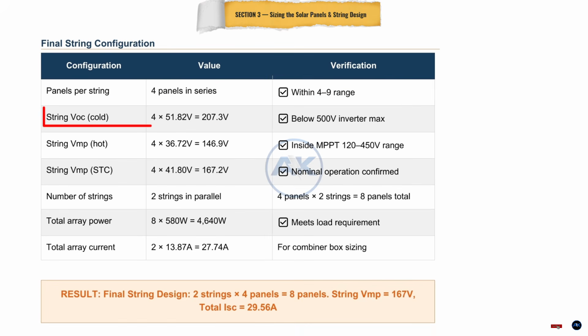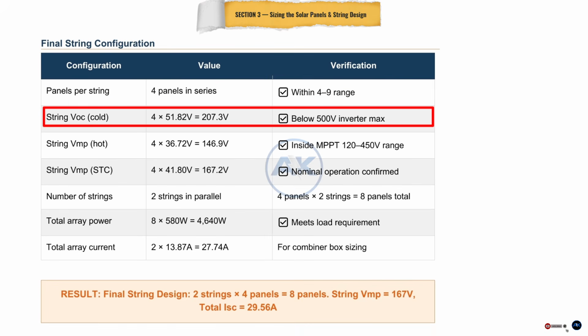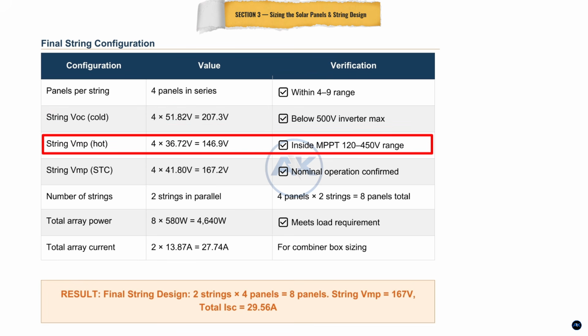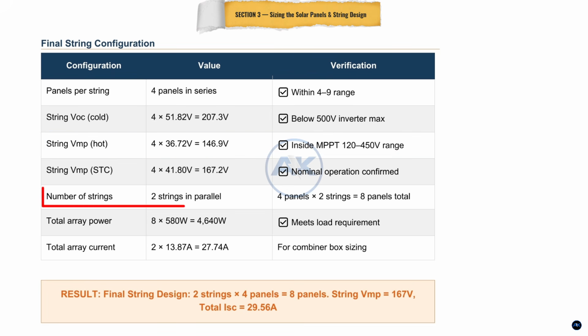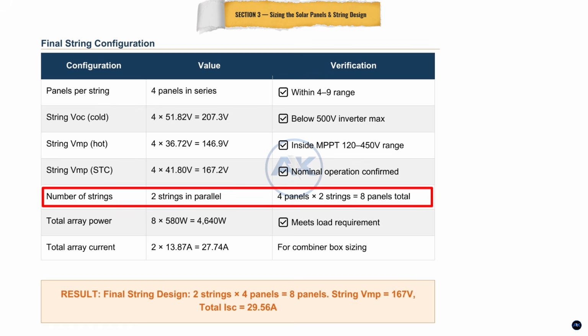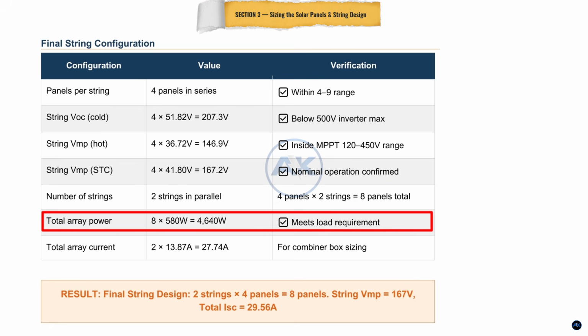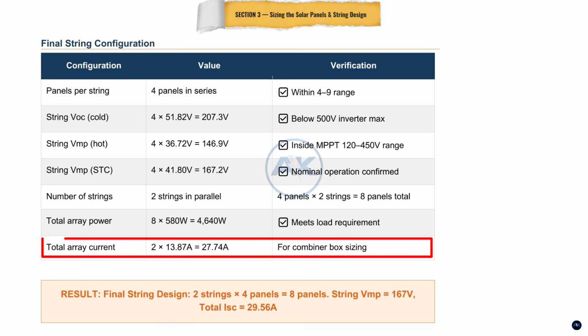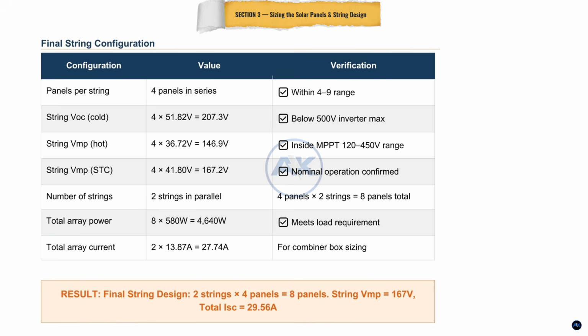String VOC cold is 207 volts, safely under 500. String VMP hot is 147 volts, inside the MPPT range. Perfect. We run 2 strings in parallel, giving us 8 panels total, 4,640 watts of solar power. The combined array current is 27.74 amps flowing into the inverter MPPT input. We will use this number in the next section when we size our protection equipment.